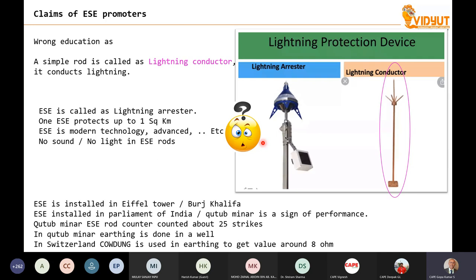Then the next point of these manufacturers is that ESE is installed in the Eiffel Tower, then the Burj Khalifa. They say the performance of ESE is very good because it is installed in the Parliament of India and Qutb Minar, and these are signs of good performance because the Parliament of India is protected. In Qutb Minar, on the ESE rod, there is an earthing, and there is a counter which counted, I think, up to 10-15 strikes. I remember it is something like 25 strikes. The counter has counted 25 lightning strikes on this lightning arrestor, the ESE rod. That means lightning has struck it 25 times and nothing happened to the building.